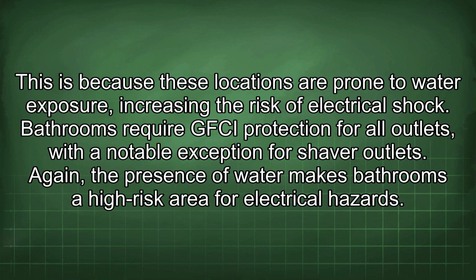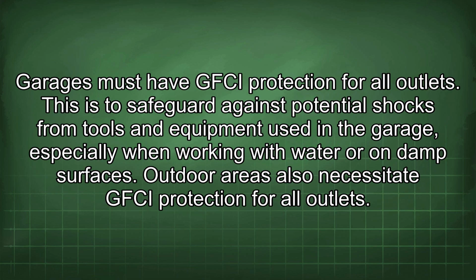Bathrooms require GFCI protection for all outlets, with a notable exception for shaver outlets. Again, the presence of water makes bathrooms a high-risk area for electrical hazards. Garages must have GFCI protection for all outlets. This is to safeguard against potential shocks from tools and equipment used in the garage, especially when working with water or on damp surfaces. Outdoor areas also necessitate GFCI protection for all outlets.